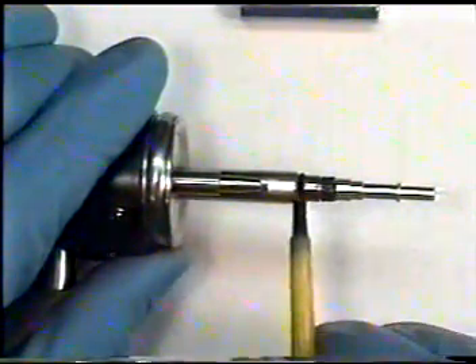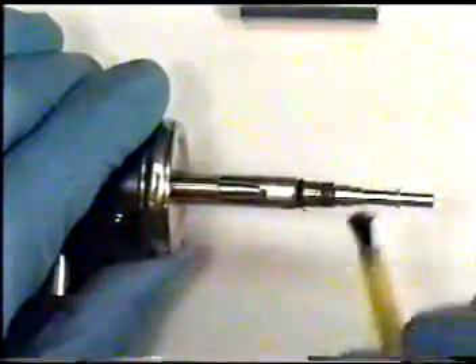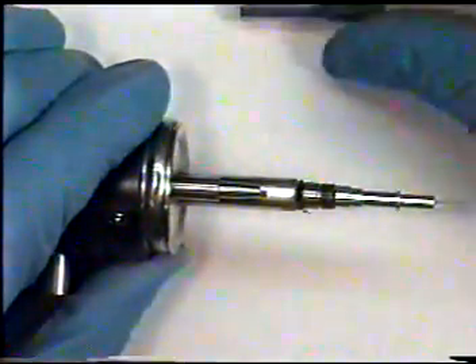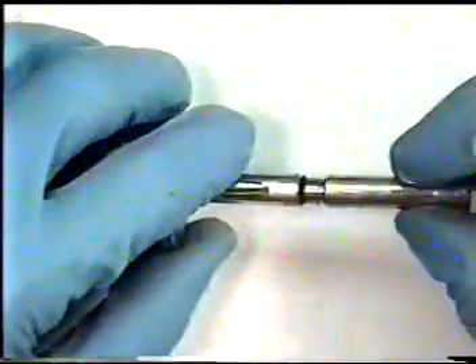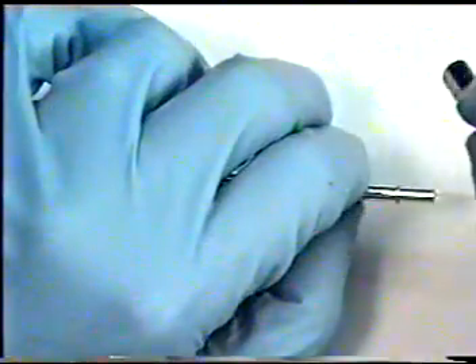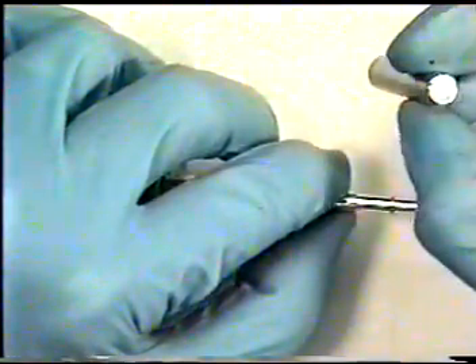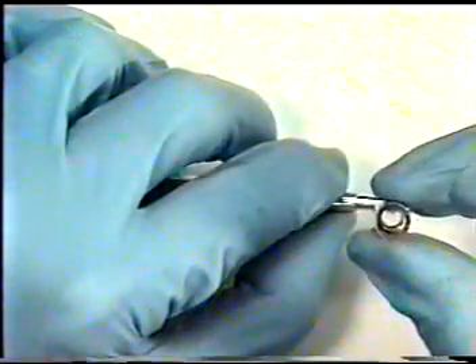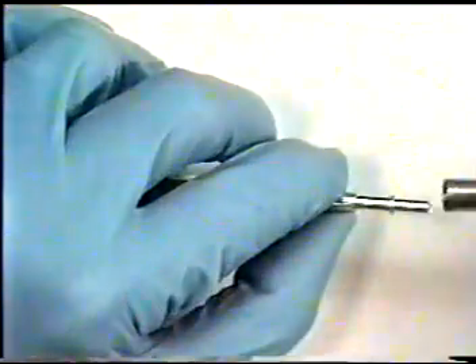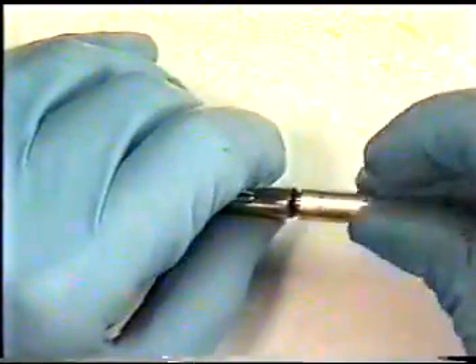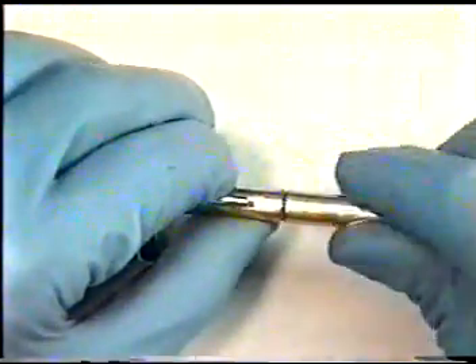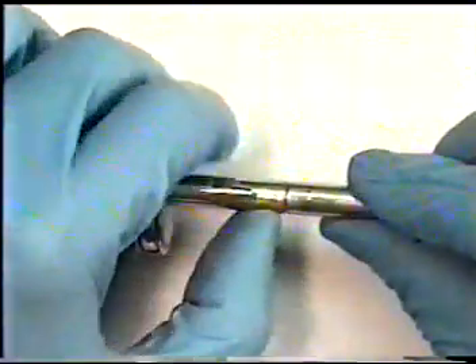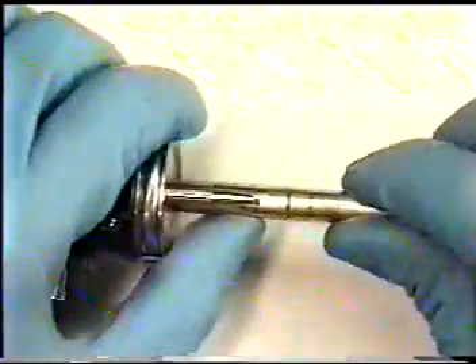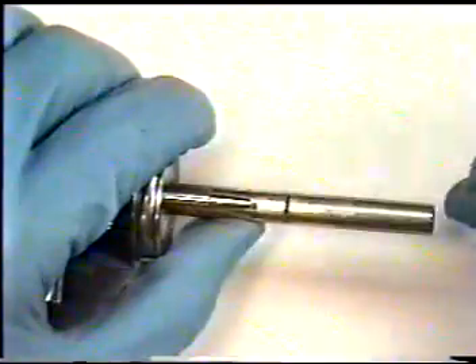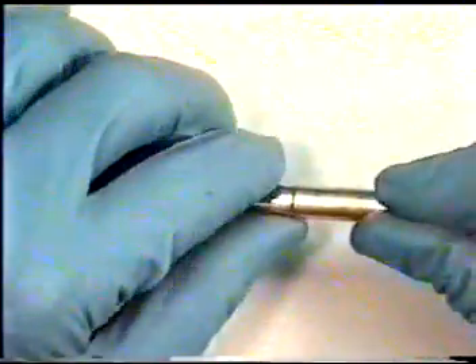Using a small paintbrush, apply some white lithium grease around the O-ring, removing any debris that may cause an air leak. Carefully slide back on your light guide probe sleeve, being sure that it is clean internally with no debris. Sliding it up and over while holding it on, allowing the grooves to fit and for the end piece to screw on flush to your proximal fitting. If it does not, it means that the grooves are not lining up on your new light guide bundle.